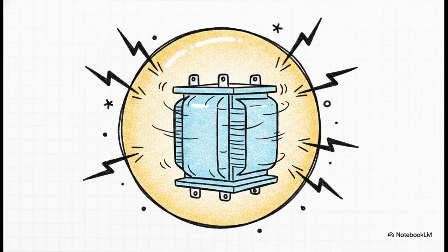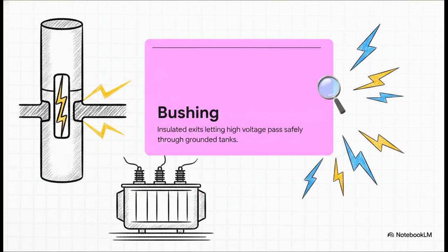Okay, let's dive into this checklist. Think of this external hardware as a dedicated team of bodyguards. Inside a transformer, you've got a highly vulnerable $50,000 plus magnetic core and these tightly wound coils. But outside, you have the wild, unpredictable forces of nature and severe electrical grid transients. The components we're about to explore are specifically engineered to sacrifice themselves or to just clamp down on dangerous anomalies long before those forces can ever reach the winding insulation and cause a catastrophic, incredibly expensive failure. So let's look at our first line of defense, the bushings.